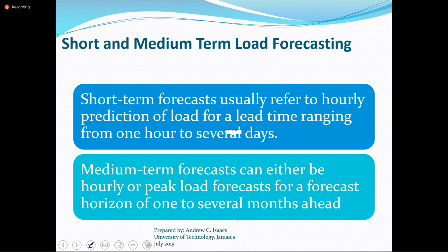A lot of the maintenance will take place around March, April, May, because that is the low demand period. But you certainly would not want to be taking out units during the summer for maintenance, because that's one of our major peak periods as far as demand is concerned. Similarly, you wouldn't want to be taking it out November through to about early March, because that again is our winter tourist season.